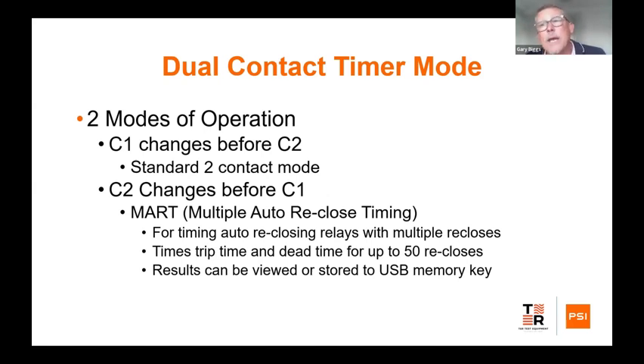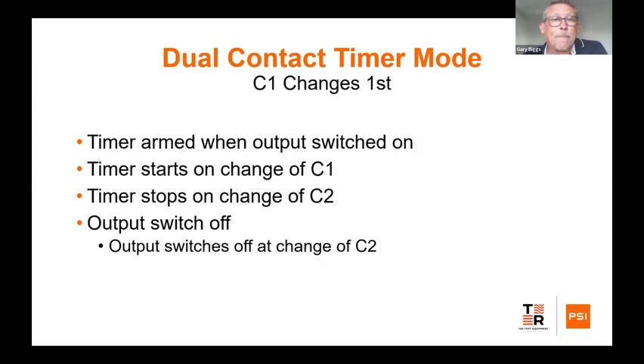So it'll be C2, it'll then operate the relay. C1 will operate it to come back on again. C2 will operate, and so on and so forth. Now, our test set will allow us to test up to 50 auto opens and closes of those types of relays. And the results then would be stored on a USB memory. As I said, most auto reclosers won't operate 50 times. They'll do 5 times on the trot, and after 5 times they give up and say, no, that line has an issue. We need to go out and fault find on that issue.